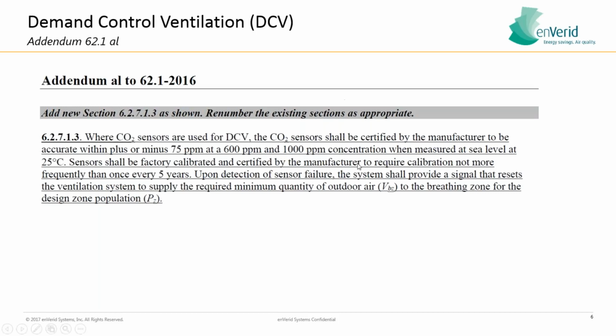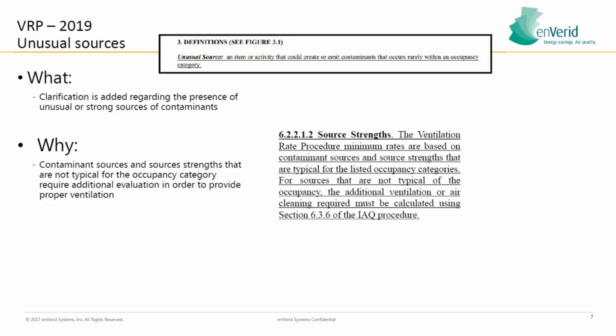And you can no longer use sensors that need frequent calibration. These sensors have to be manufacturer certified to not require calibration more frequently than once every 5 years. Very few sensors on the market for demand control ventilation right now meet these two requirements. So be very aware that for ASHRAE 2019, these are two new requirements that are very constricting for demand control ventilation, okay? For ventilation rate procedure 2019, this is a big change.